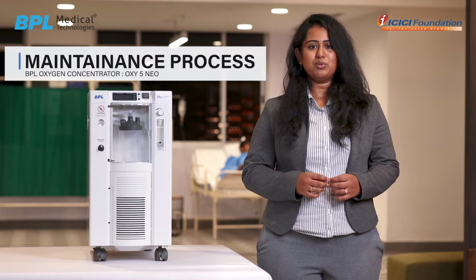Hello everyone, in this video we are going to see the maintenance part of the oxygen concentrator. BPL oxygen concentrators provide 5 liters per minute continuous flow oxygen of concentration 93%. This model is CE certified, which meets patient safety and environmental requirements. The oxygen concentrator is specially designed to minimize routine preventive maintenance. Oxy 5 Neo has heavy-duty compressors with thermal protection and also has pressure relief valves which ensures patient safety.